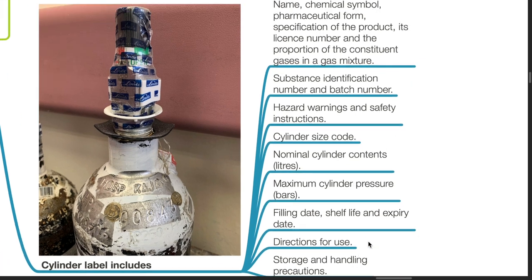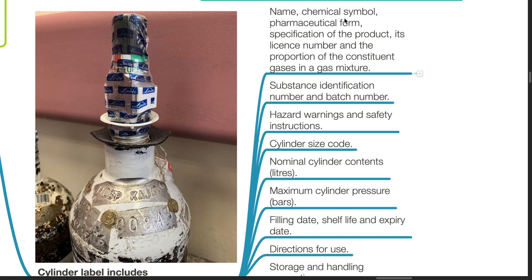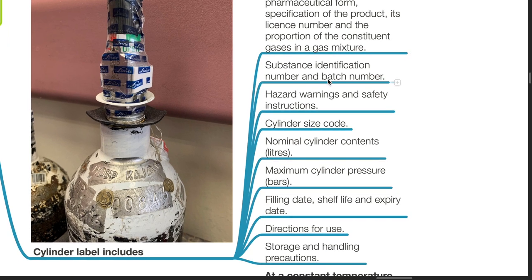Cylinder label includes the name, chemical symbol, pharmaceutical form, specification of the product, its license number, the proportion of the constituent gases in a gas mixture, substance identification number and batch number, hazard warnings and safety instructions, cylinder size code, nominal cylinder contents in litres, maximum cylinder pressure in bars, filling date, shelf life and expiry date, direction for use, storage and handling precautions.